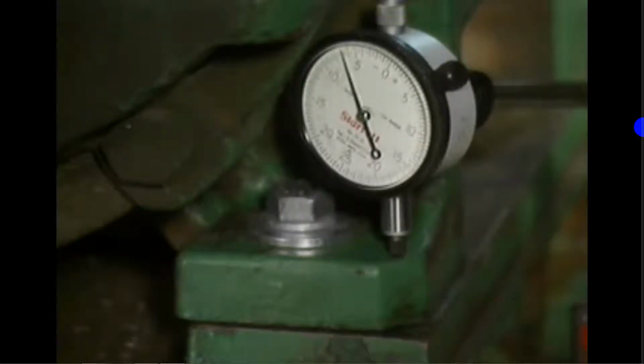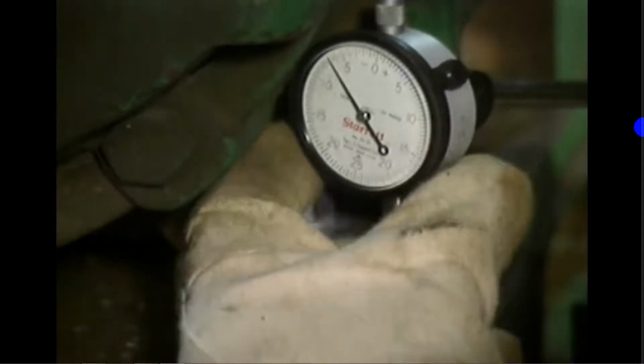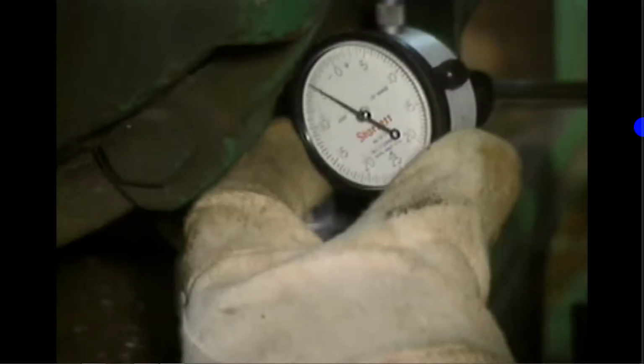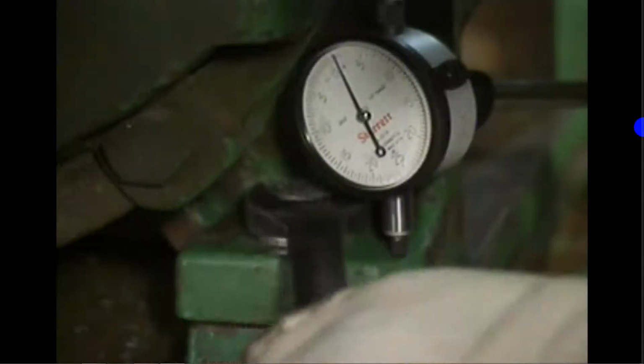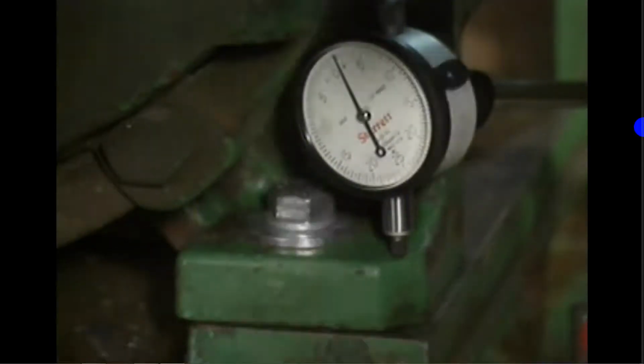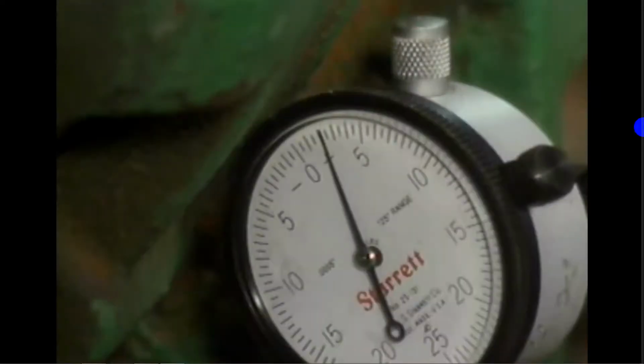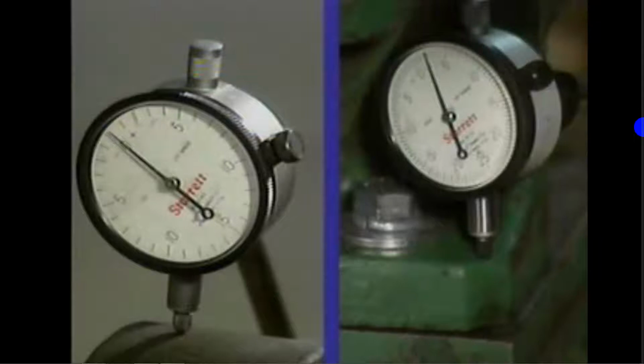Each dial indicator is mounted so that its stem is partially compressed before the indicator is zeroed. Doing this ensures that each dial indicator will be able to detect movement during the procedure. Next, the hold-down bolt on the first foot is loosened and the dial indicators are checked. If either dial indicator detects more than the allowable limit of movement, which at many plants is 2 mils, then the foot is soft. To understand why 2 dial indicators are preferable, we need to look at some illustrations.